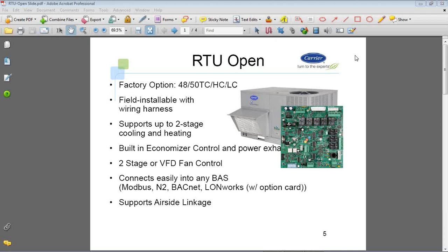Just a couple features of the controller. It can support up to 2 stages of heat, 2 stages of cool, full economizer, and power exhaust. Sorry, that got cut off there. I'm not sure how many of you are familiar, but the new Carrier rooftops are coming out with 2-stage fan control, where you would purchase a Carrier rooftop unit with a VFD on it, and it would be able to stage the fan for first stage cooling, second stage cooling. All of that logic is built into these controllers. There's nothing custom you have to do to it. It will just come ready to go. It's an option you'll select, and we'll look at that a little bit later here.